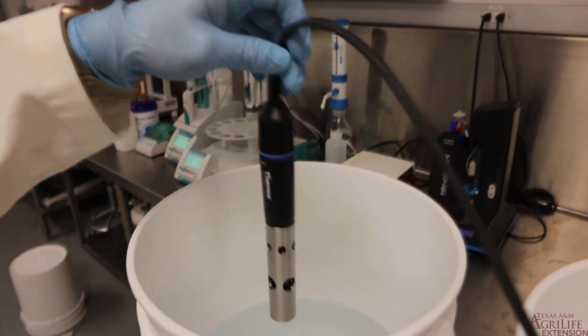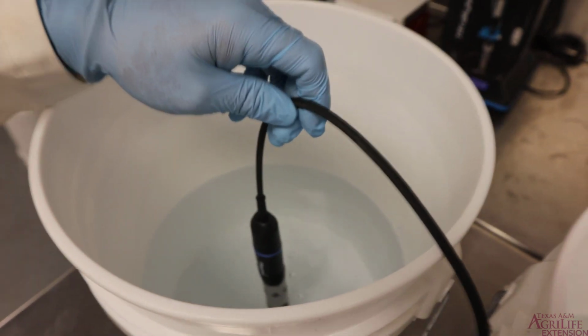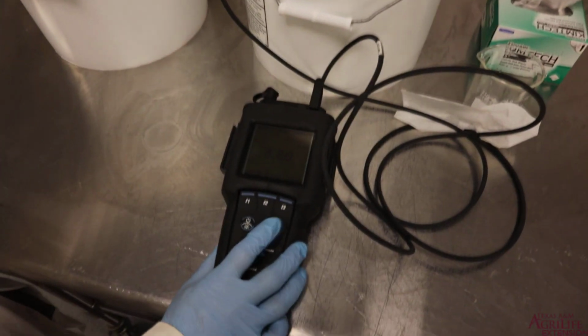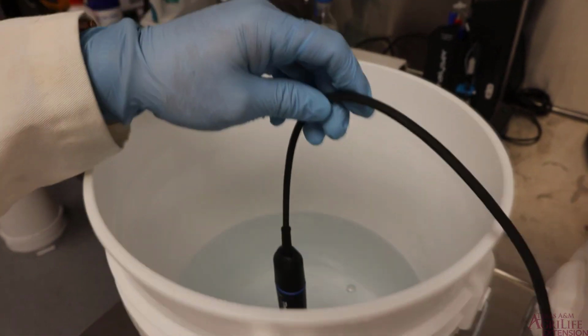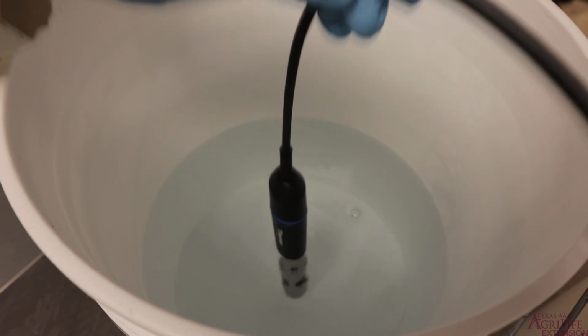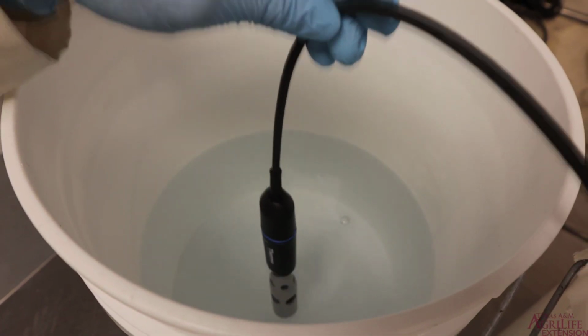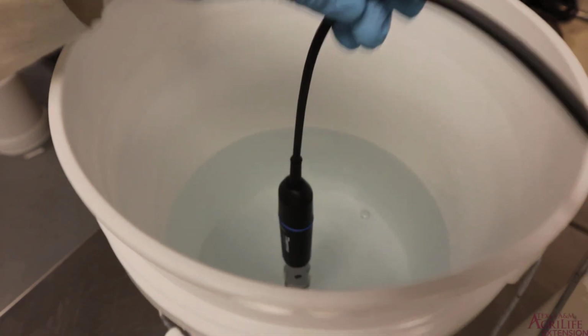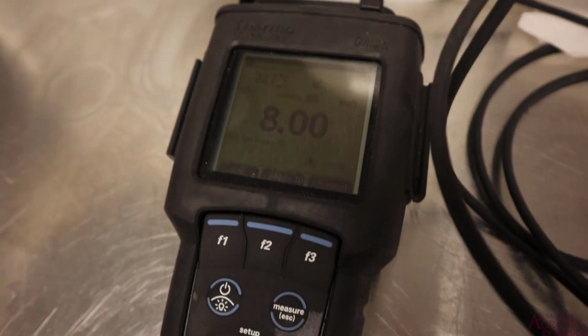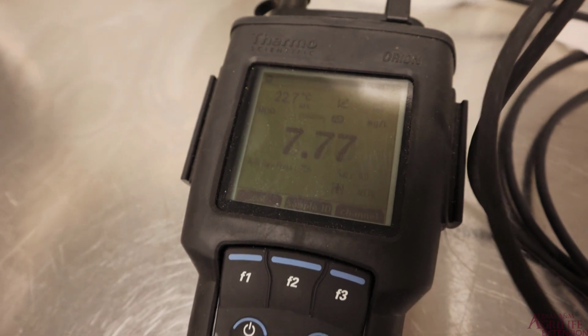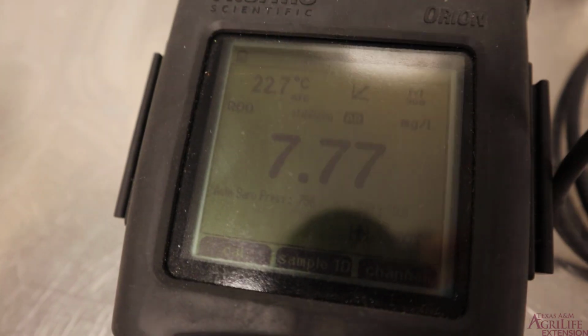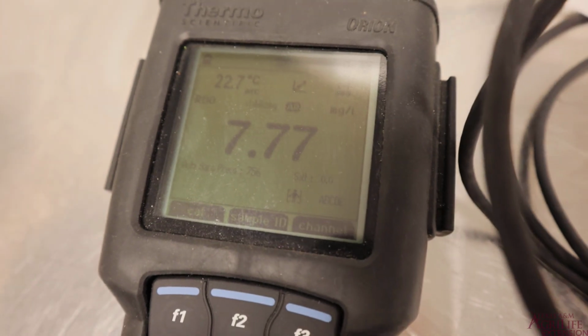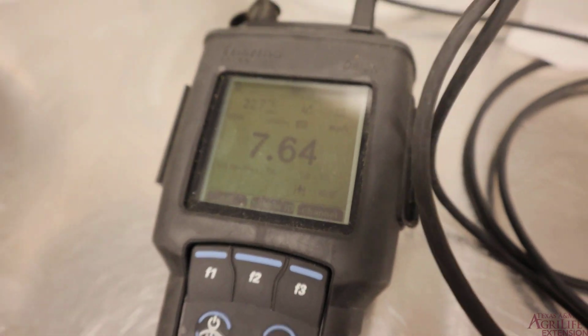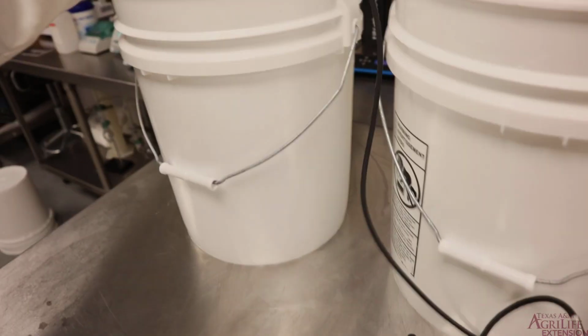Alright, so we'll go ahead and drop our probe down into our tank. We will start to hit the measure button, and then we'll gently bob our probe up and down while it is measuring. This should take anywhere from probably 2 to 5 minutes, especially if you have a lower DO level in your tank, somewhere around 1 milligram per liter or less.